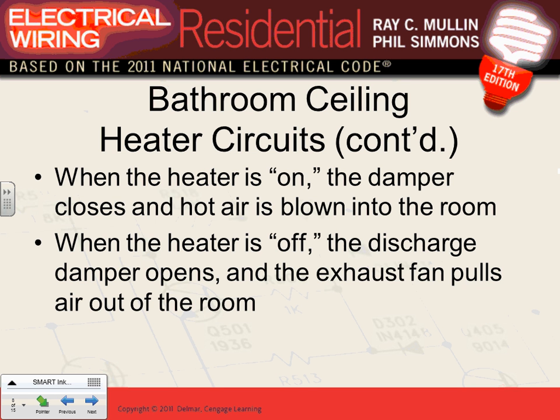So, okay. This is just how it works, guys. They have a damper inside. So if the exhaust fan is on by itself, the damper will open and you exhaust all these fumes and all this bad stuff from the bathroom to the outside. If the exhaust fan is on and the heater is on, you close the damper and you start dumping all this hot air down to heat you. That's how it works, by interlocking inside the equipment.